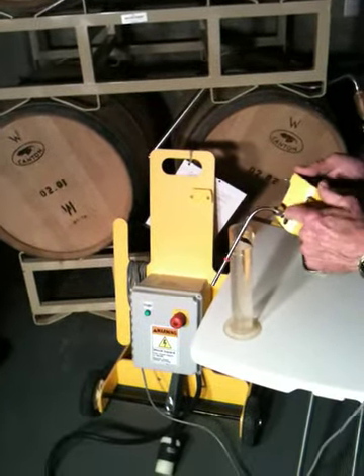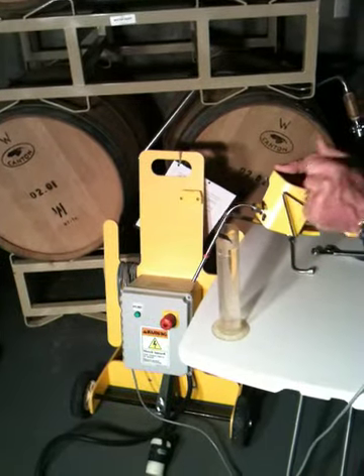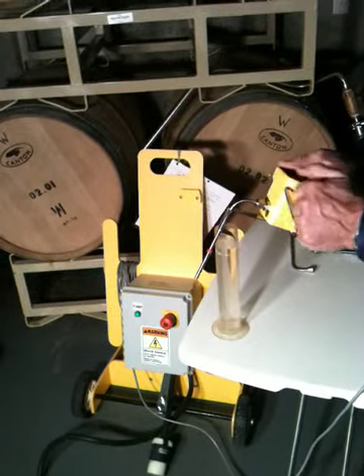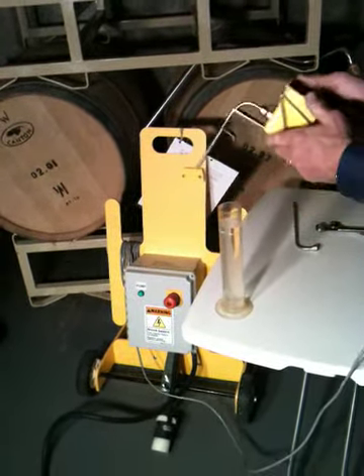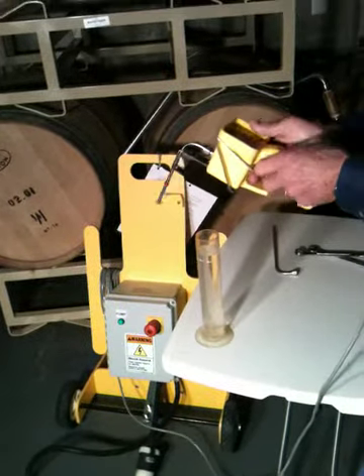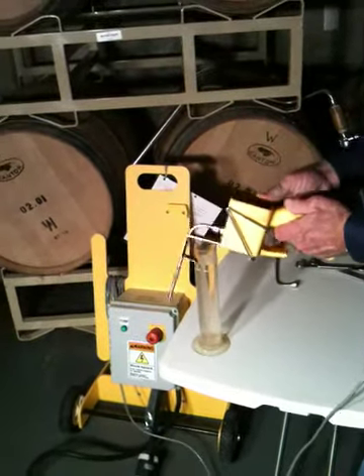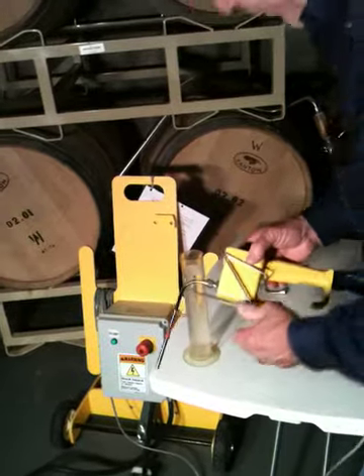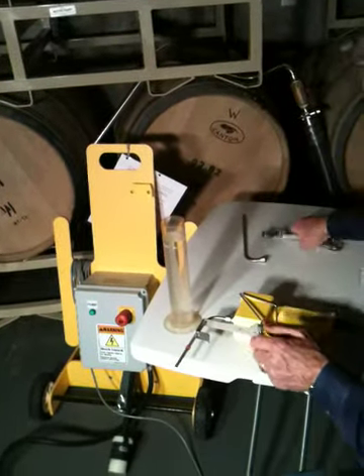Use a 5/8 wrench here on the body and a 9/16 wrench on the nut. Tighten a little bit more. If it didn't pass the leak test, then you go back to it again. So we'll try that one more time. But let's do that after we put a new sensor on. I want to demonstrate how simple it is to change the sensor out.